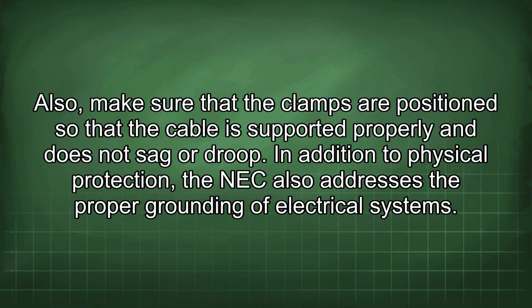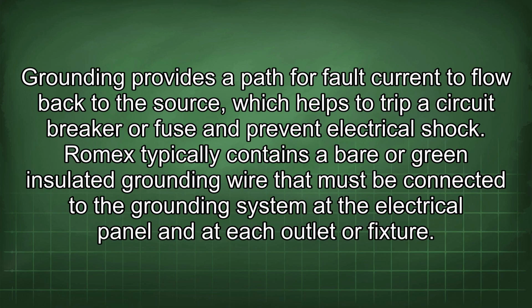In addition to physical protection, the NEC also addresses the proper grounding of electrical systems. Grounding provides a path for fault current to flow back to the source, which helps to trip a circuit breaker or fuse and prevent electrical shock. Romex typically contains a bare or green insulated grounding wire that must be connected to the grounding system at the electrical panel and at each outlet or fixture.